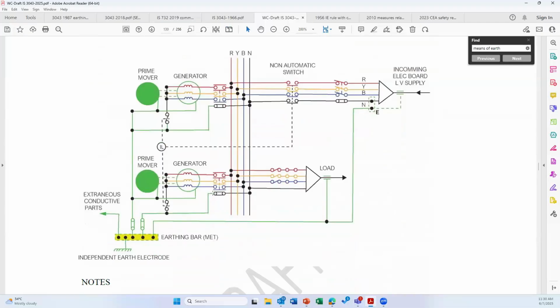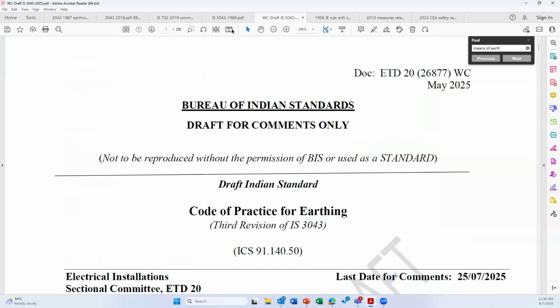Now, please note that these are not new pictures. These have existed in the standard for several decades. But instead of following this correct way, we were following a different way. One of the reasons was that sometimes state electrical inspectorate engineers were demanding a separate earth pit for neutral and a separate earth pit for body. However, as I said, these demands were due to the old definition in the CEA regulation, which was already updated in 2023. So the chance of misinterpretation of the definition or of the contents is already gone. Very clear definitions, very clear information are already in the standard now.